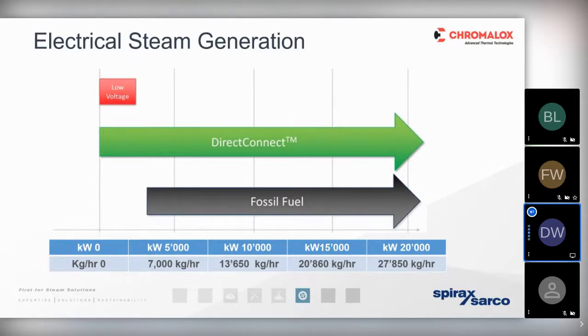And it's really just a question of ensuring that the appropriate electrical heater element is selected in order to match the required mass of steam that's required by the process. So an electrical generator can very easily be incorporated again into an existing steam boiler house, as perhaps the fossil fuel steam burner can be retrofit with the appropriately sized electrical element. In other words, we can carry on using the same steam boiler, the same infrastructure, the same distribution network, and maybe even the same water treatment plant.